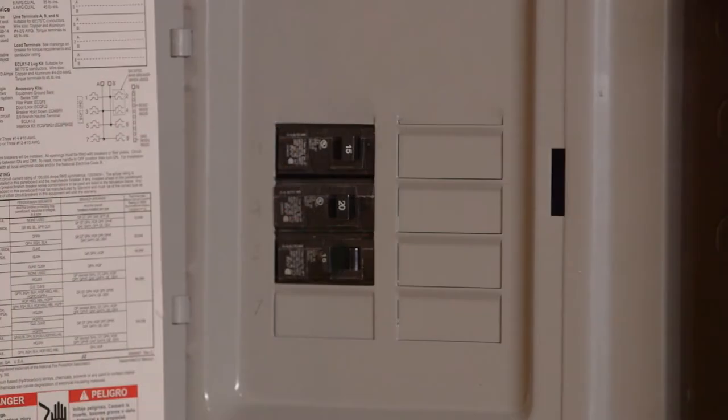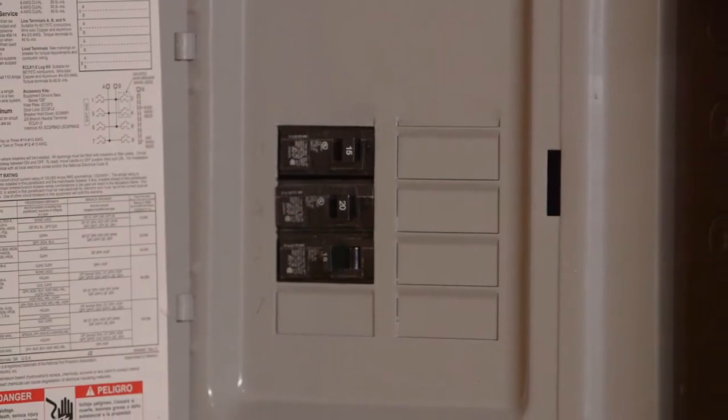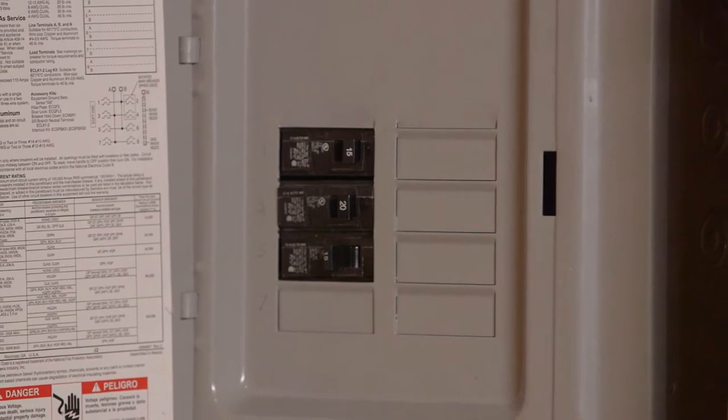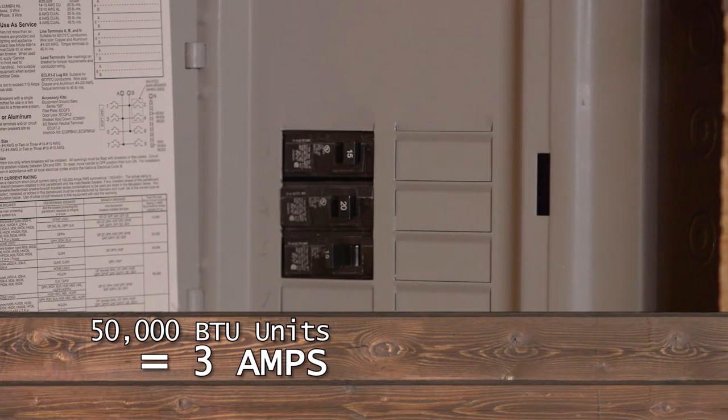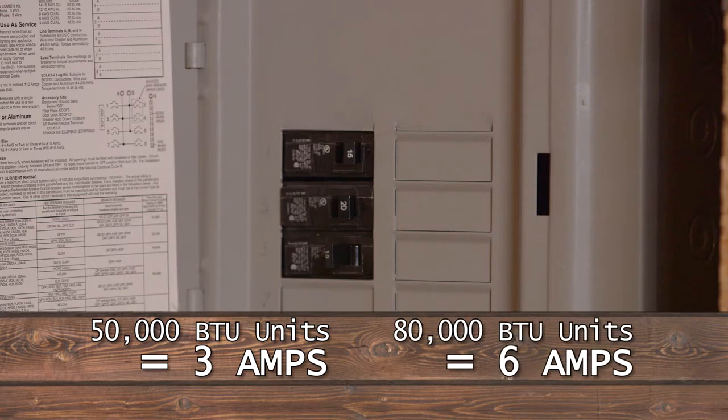Electrical connection requires a minimum of 15 amp service. 50,000 BTU units draw 3 amps, while 80,000 BTU units draw 6 amps.